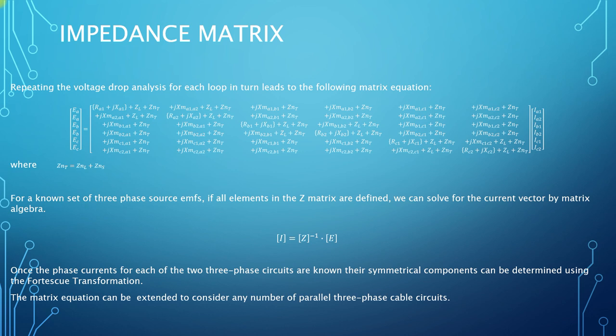For a known set of source EMFs, the currents in each of the six conductors can be calculated. Once the currents in each of the two three-phase circuits are known, their symmetrical components can be determined using Fortescue's transformation. This matrix equation method can be extended to consider any number of parallel three-phase circuits.